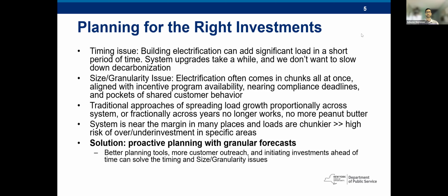The second major issue is a size and granularity issue. Electrification is coming in big chunks nowadays. It's not a smooth adoption of a new technology, like people switching from radios to TVs, or adding extra lights to their house. We're having huge chunk loads coming in, where people switch from, say, natural gas heating to a 5 kilowatt heat pump overnight. That's a big change, and we need to stay ahead of it. The granularity issue is that these loads aren't happening everywhere all at once. These big chunky loads are dropping into a single point on a feeder, or a single node inside a broader system, and you need to know where that is.